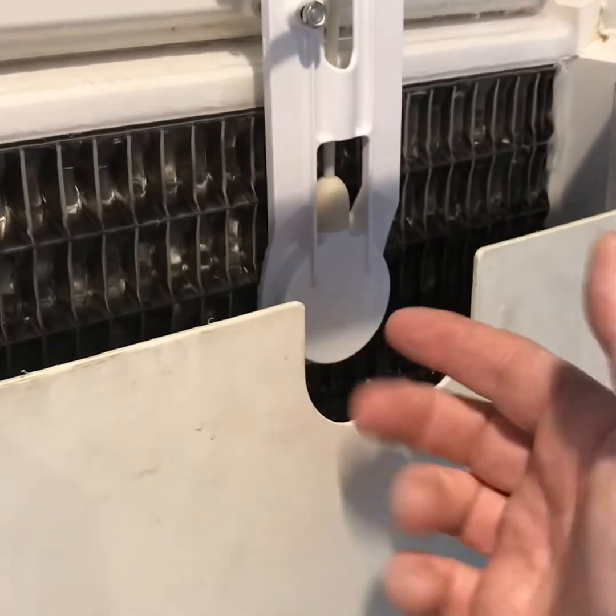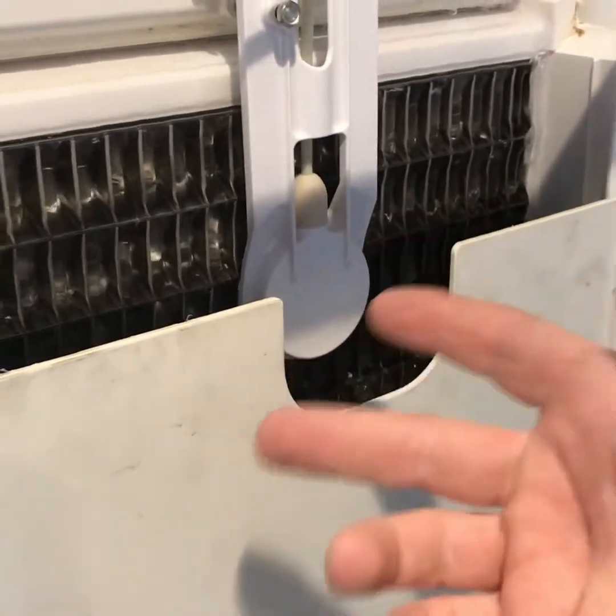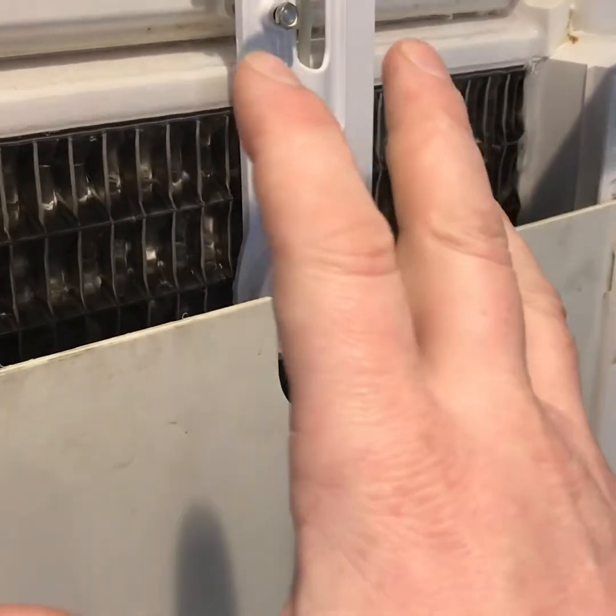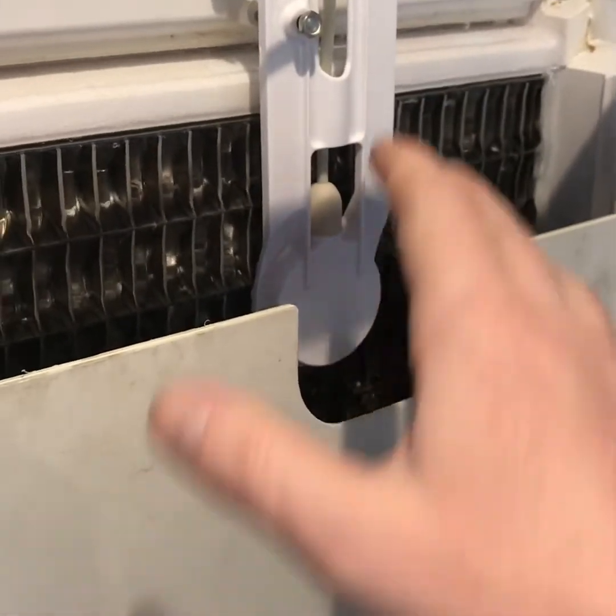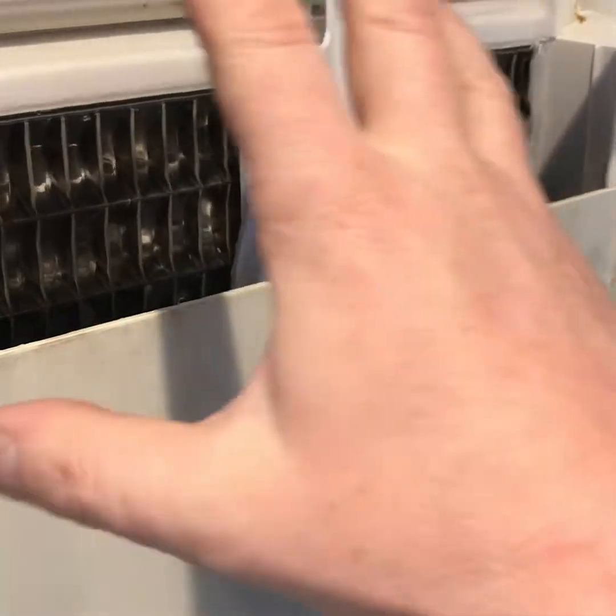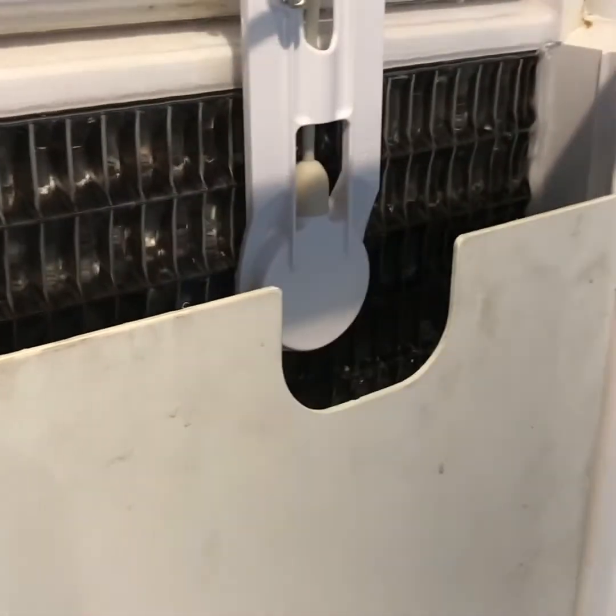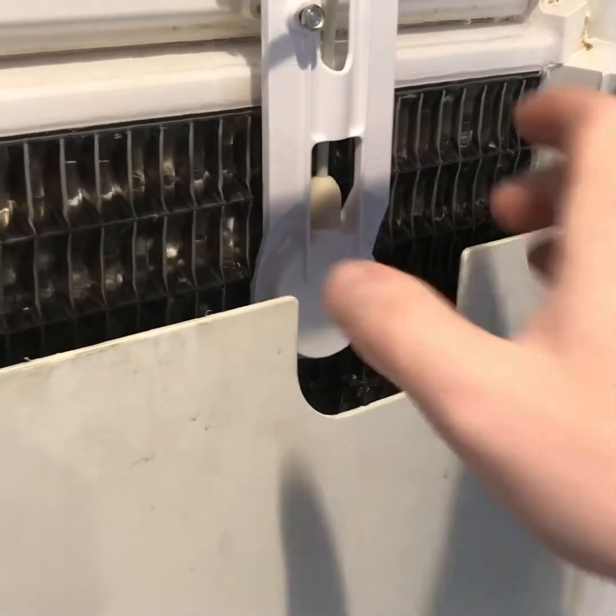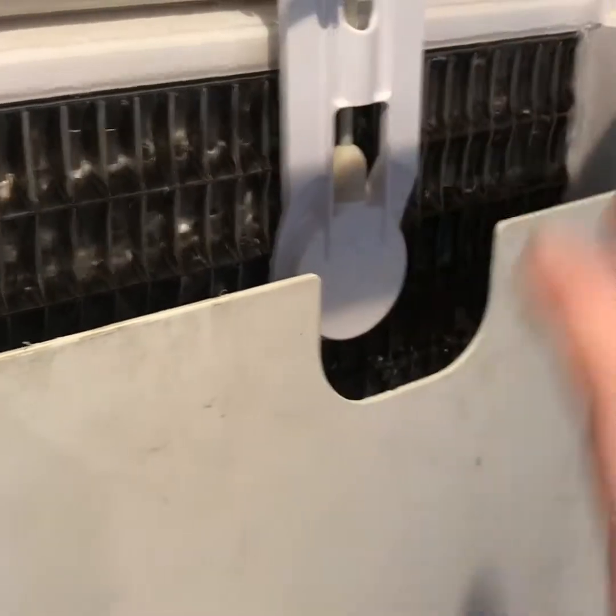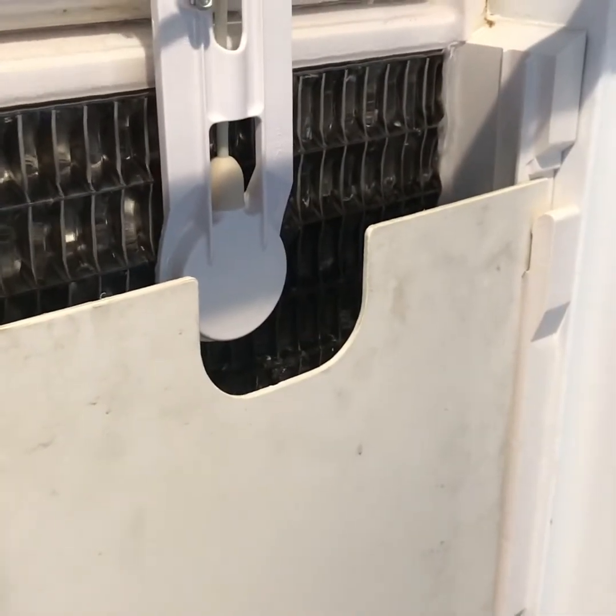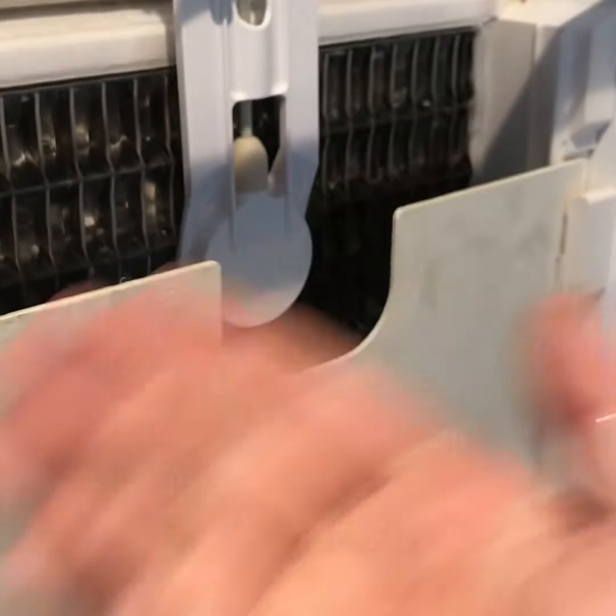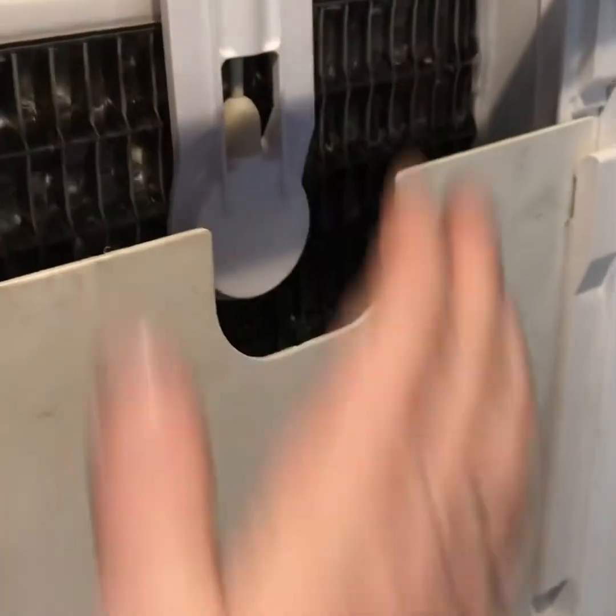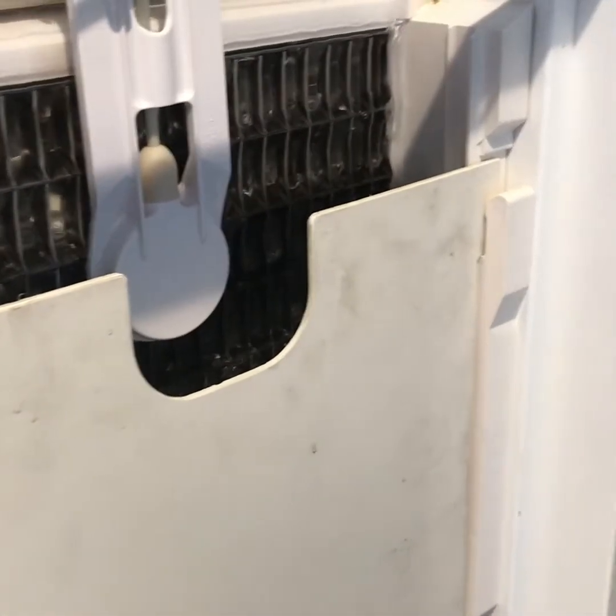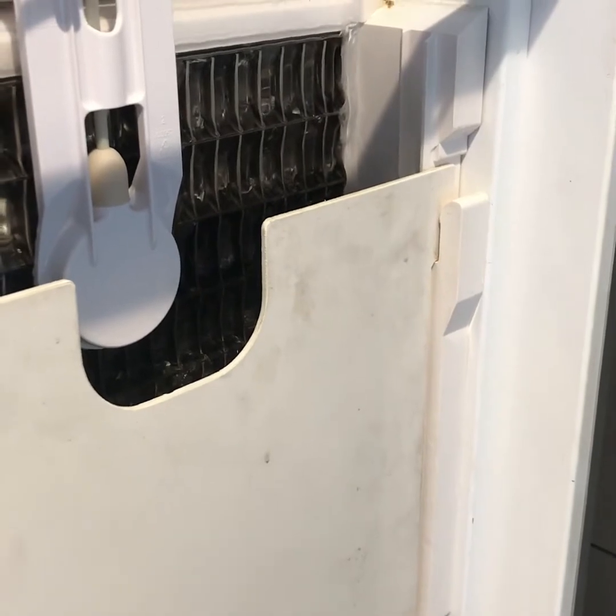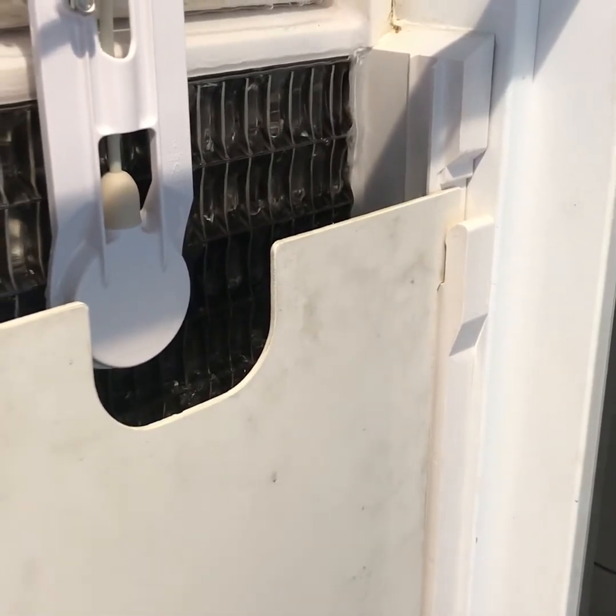These ones don't really get dirty. I mean, they do, but it doesn't really affect the operation -- this thing can be just filthy and the unit will still run. But the old style was definitely not the case. Those things got built up with even corrosion on the cover where it faced against the ice machine, and it would not go into a harvest, and it would build a big chunk of ice.